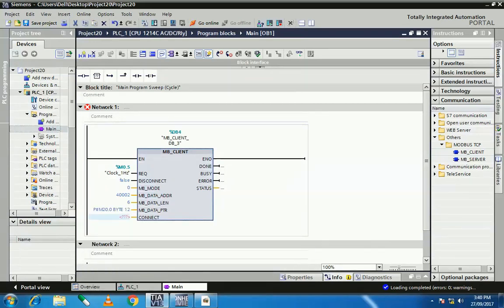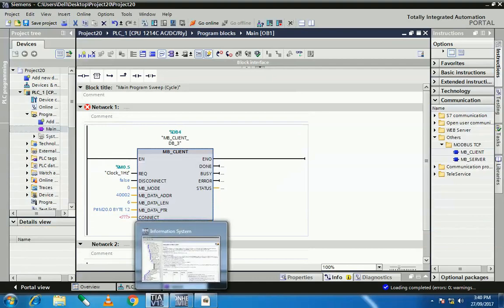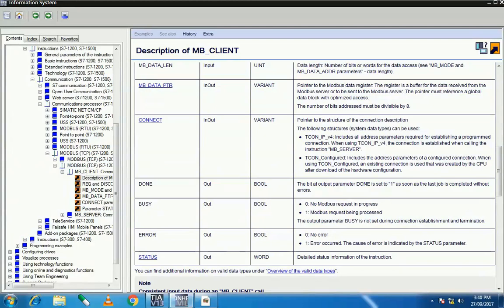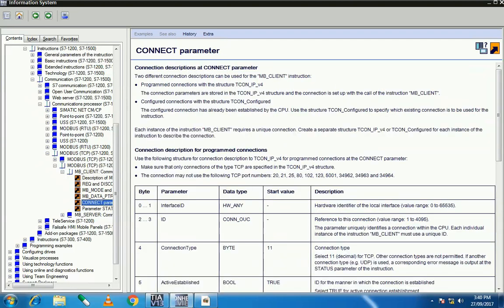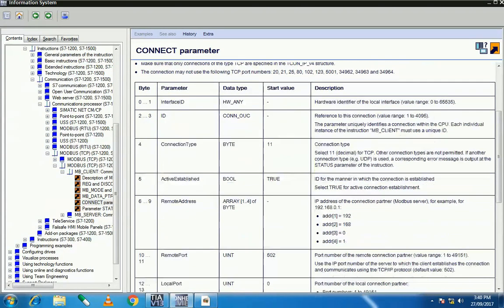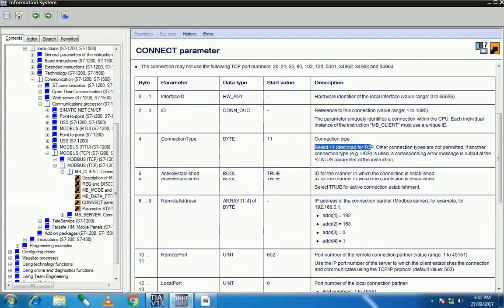Next is the connect block. I will show you information about the connection. We use the data type TCON_IPv4. In the connect options, we set all configuration about our client. The interface ID is the hardware identification number of the local interface. The ID is the reference to the connection. For the connection type, we are using TCP/IP, so we set 11 for a TCP connection.